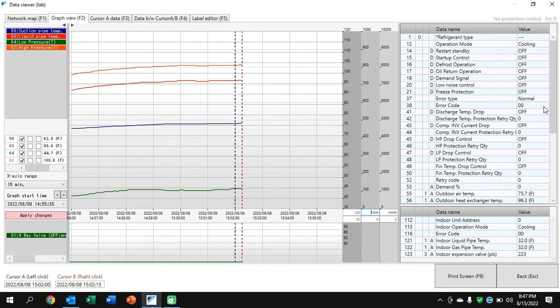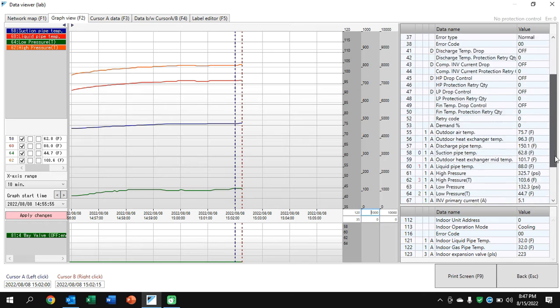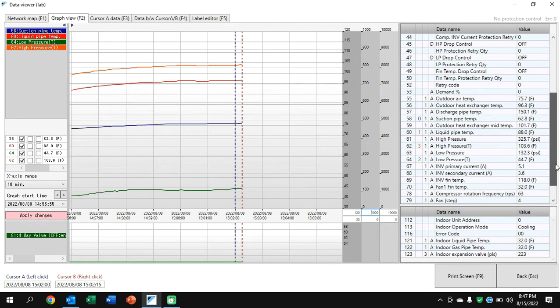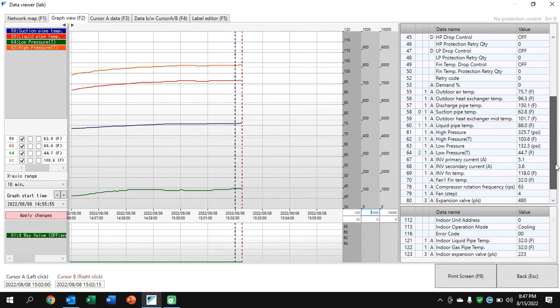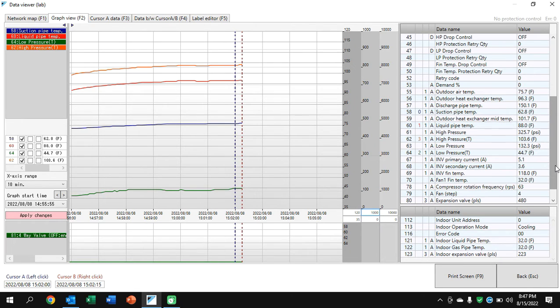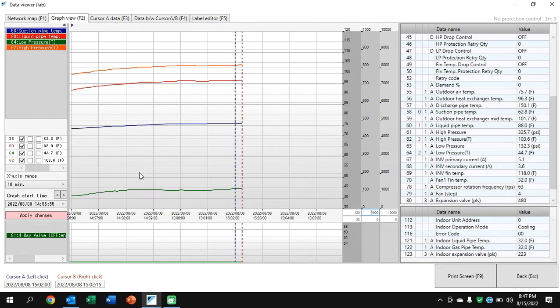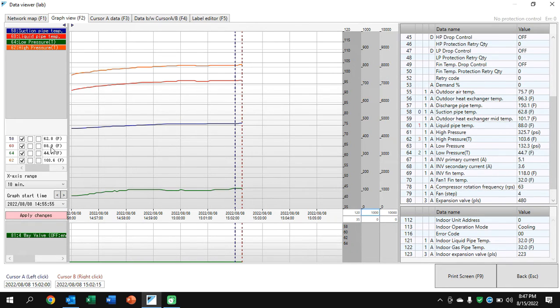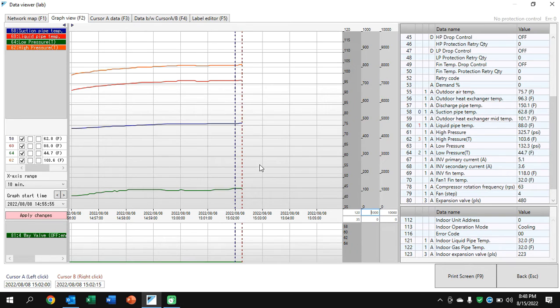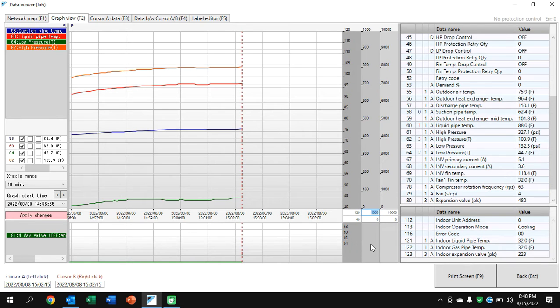It'll turn on and off. It'll see the update. And this is a method to monitor the superheat and the subcool as we're running the system. We'll see a small splice here or there. I didn't want to lose continuity. But a lot of the data I did not have to have continue running. And we'll see here, I'm just during the use as I'm recording this. I'm actually recording my screen. I want to really pay close attention to that spread between those numbers. It's not as large as you actually think. You'll have to actually look at the superheat and subcool as listed in the actual data. And just note that the chart, the script changes, may just be for you to watch closely. And when you start seeing a swing to look back at the numbers.